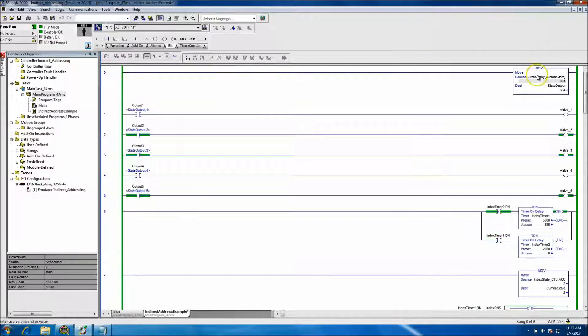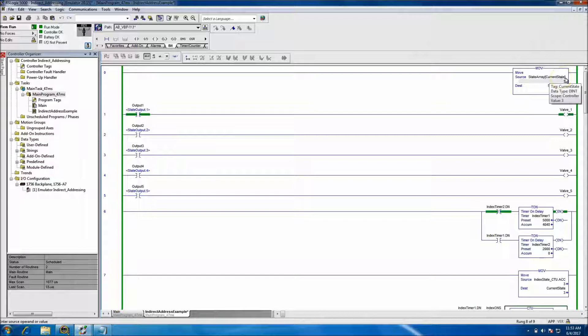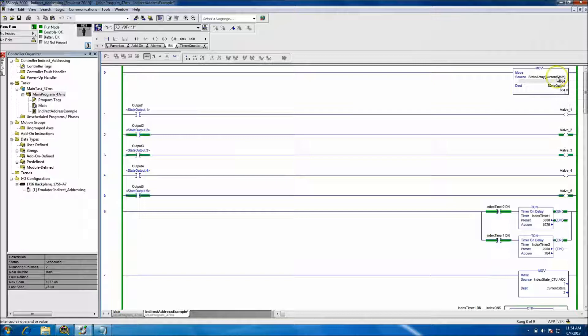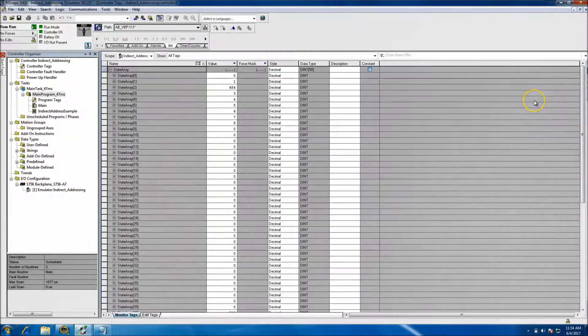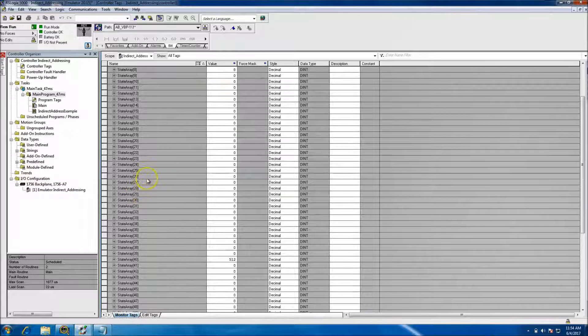Basically what's happening is we do a move, and in that move we have brackets — whatever is in the brackets is another tag, closed by a closing bracket. Whatever value is in the current state is making the state array index. So basically what's in the current state gets translated to the array state, and that gets moved into the destination. The current state right now is three. Looking at the array, we currently have 0 to 49 — basically 50 words.